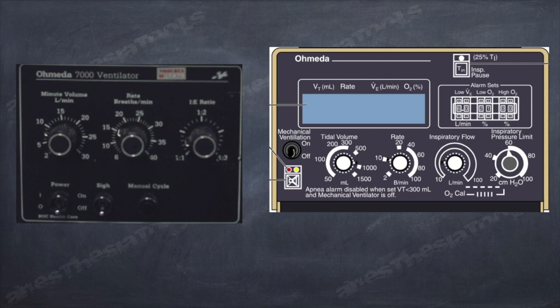In the first ventilator, we can set the minute volume and rate. Further, you have the knob to control I:E ratio also. In the next ventilator, we are asked to set the tidal volume and rate, and minute volume becomes the dependent variable. By controlling the inspiratory flow rate, we can indirectly control the I:E ratio.